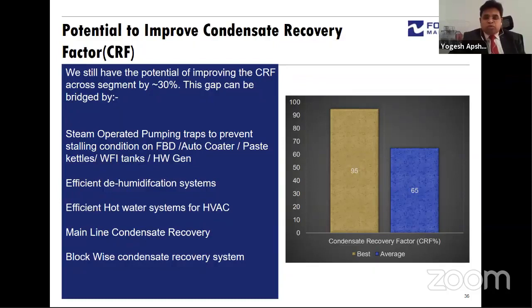Based on this, many times the condensate is drained because the quantity of condensate from each piece is not very big, maybe 100 kg or 200 kg per equipment. But if you count all these together, 200 kg from 4 or 5 equipments comes to almost 1000 kg of condensate, which is drained. Typically, the cost of condensate is 15 to 20% of the cost of steam. So it is very important to recover the condensate, which is the purest form of water. You do not need any chemical treatment if you recover the condensate back to the feed water tanks. Condensate is a distillate of the steam, so you don't need any chemical treatment. Also, the TDS of the condensate is very good, as good as very fresh water, so you don't have to add any oxygen scavenging chemicals or use a softening plant.